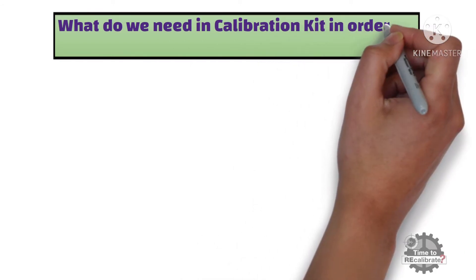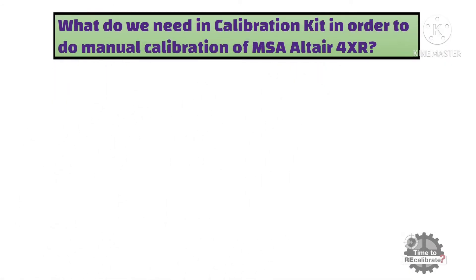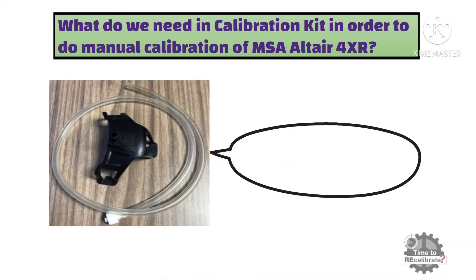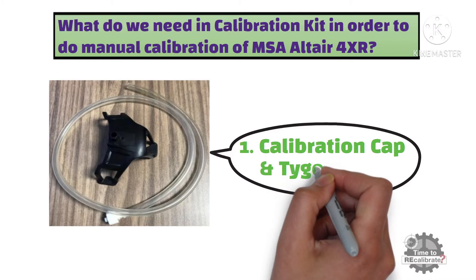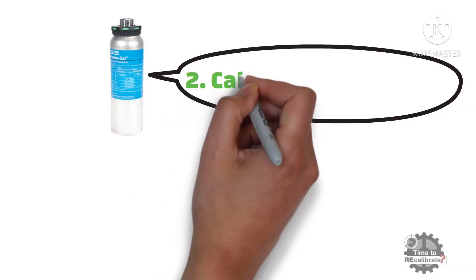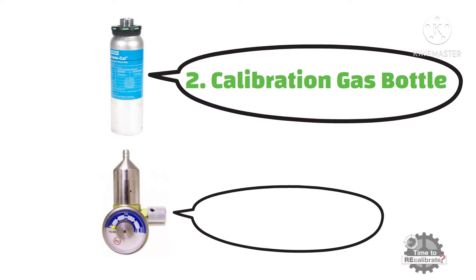First of all, what do we need in a Calibration Kit in order to do manual calibration of MSA Altair 4XR portable gas detector? First, we need a calibration cap and small Tygon tube. Secondly, we need a calibration gas bottle. Lastly, we also need a gas regulator.